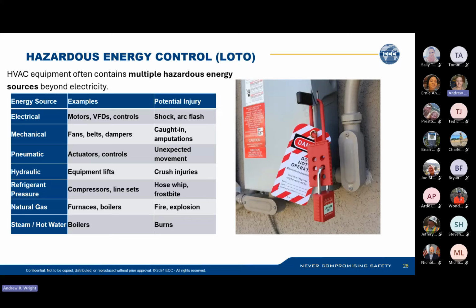I know at my last job, they sent a training tech into a big industrial air handler while it was running, and her ponytail got caught in a fan motor pulley, and it removed her ponytail. Not to get too graphic, but it's very important that you're making sure these systems are off, especially with mechanical injury, because it will keep moving with you in there or without.